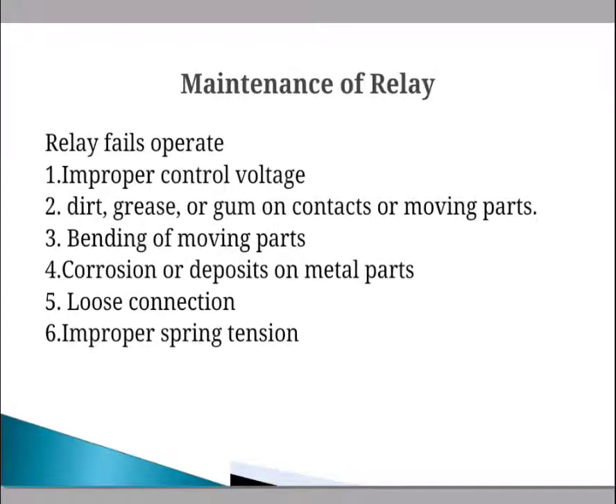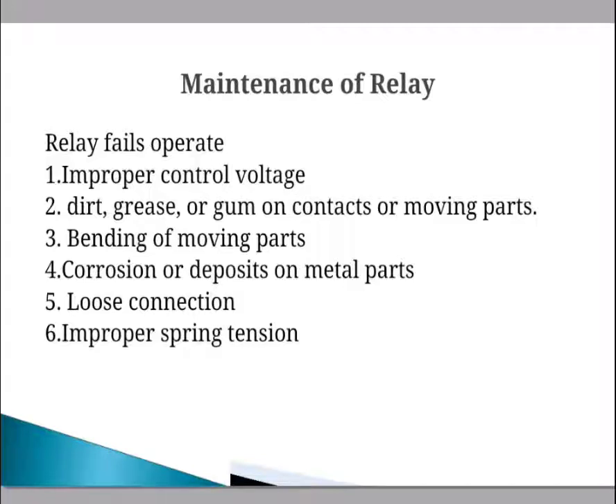When the relay fails to operate, we have to check for improper control voltage — if voltage is too low, the relay will not operate. Also check for dirt, grease, or gum on contacts or moving parts, bending of moving parts, corrosion or deposit on metallic parts, loose connections, and improper spring tension — all of these can cause the relay to fail to operate.